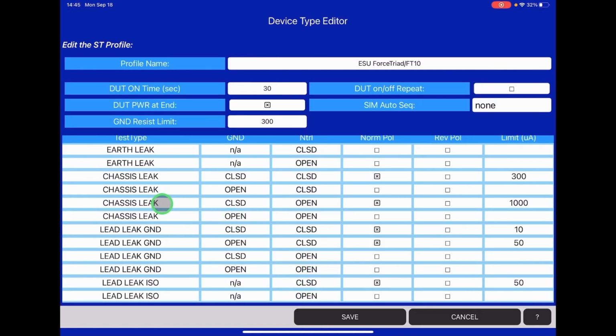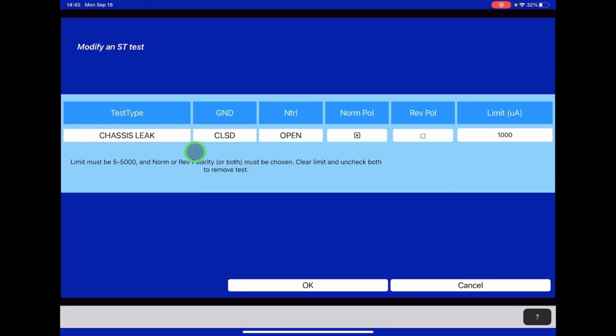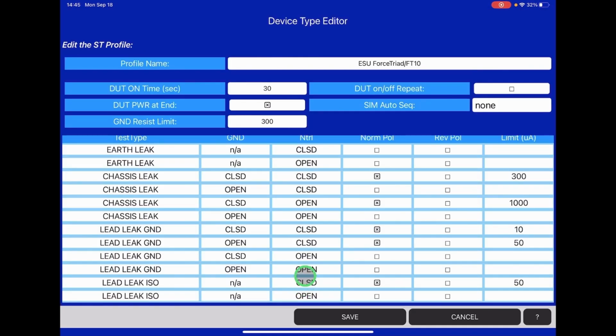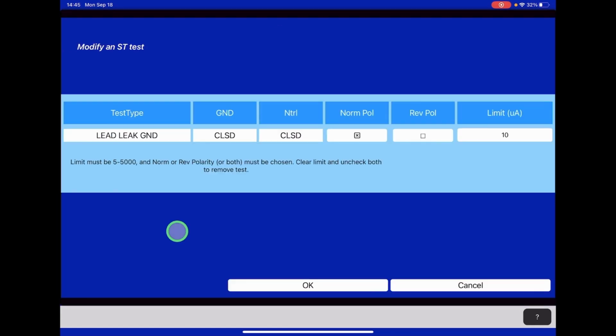The next test we need to do is a second chassis leakage test, but this time with the neutral open. That's why you see open here. Normal polarity again, no reverse polarity, and the limit for this test is 1,000 microamps. The third test down is a lead leakage to grounds test.